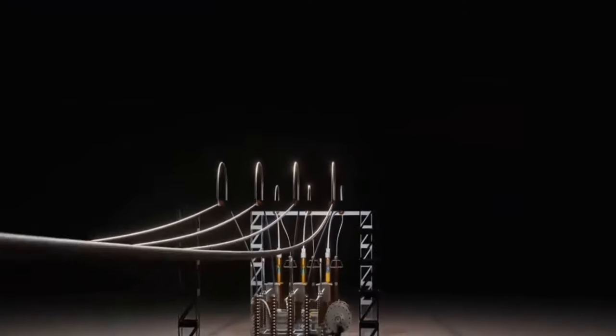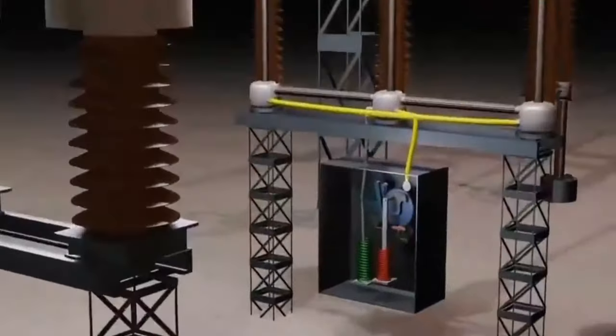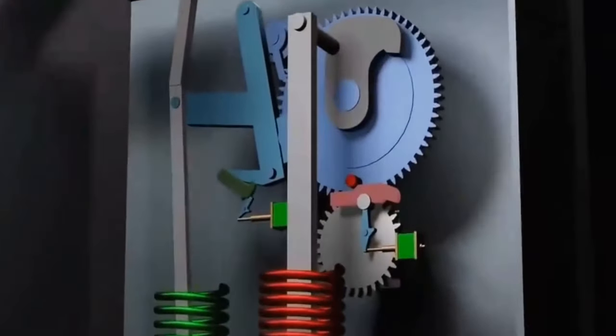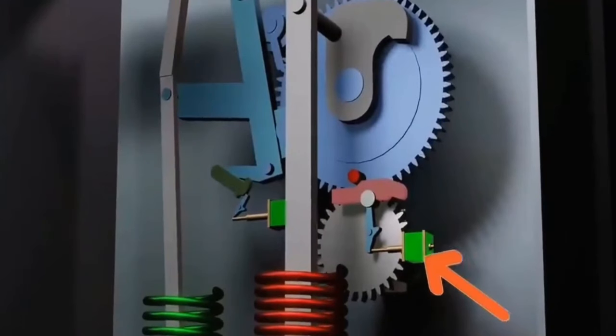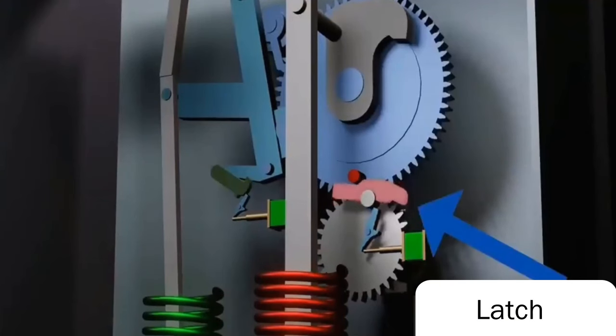So how do you reconnect the transmission line now? Let's go back to the circuit breaker. In fact, there is also a relay on the right side here, with a mechanical design identical to the one on the left. When the relay receives a signal from the control panel, the plunger of the relay triggers the latch.